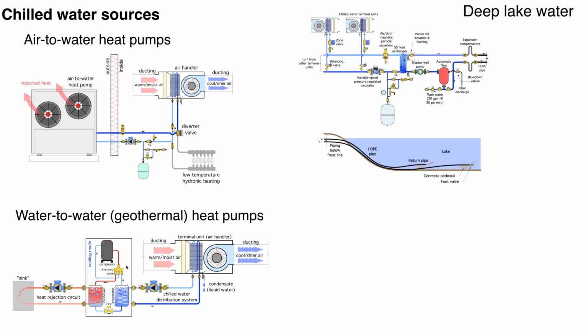Now, what are some other possibilities? One is a deep lake water system. Again, I live near the Adirondacks in upstate New York. The water temperature 20 feet down is probably still in the high 40s. Very, very capable in terms of both dehumidification and sensible cooling.